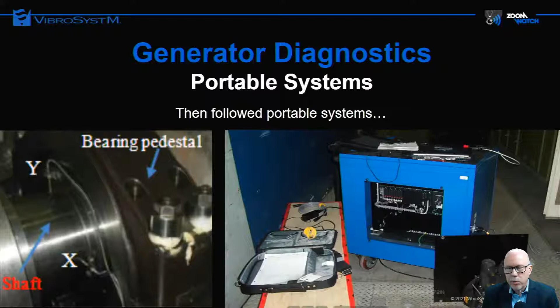The portable systems consisted of simple basic measuring chains installed and used for commissioning purposes only. These included shaft vibration probes, guide bearing absolute vibration probes, accelerometers or velocimeters, and PD acquisition devices. Usually the couplers were installed permanently, but companies would come in and take PD readings at specific times.